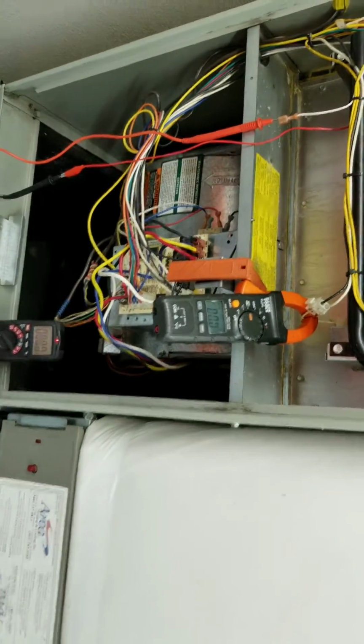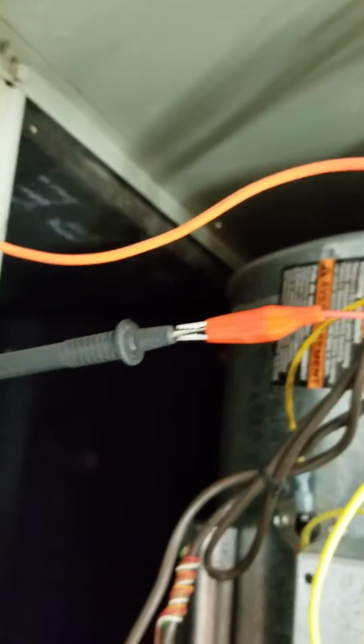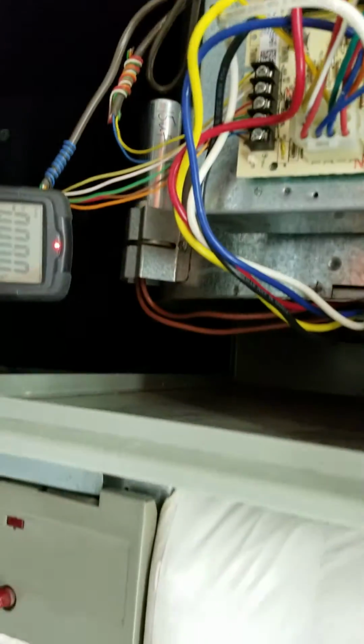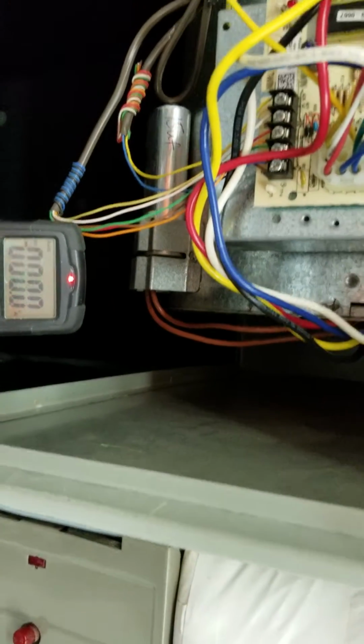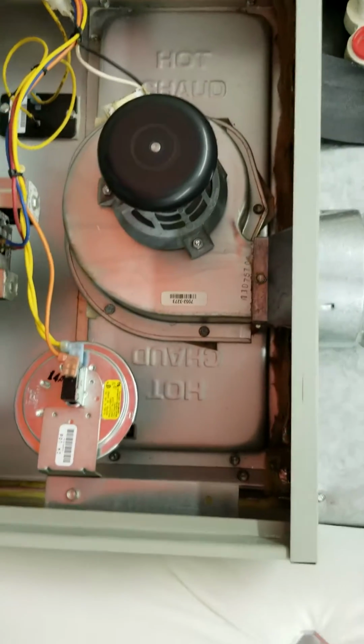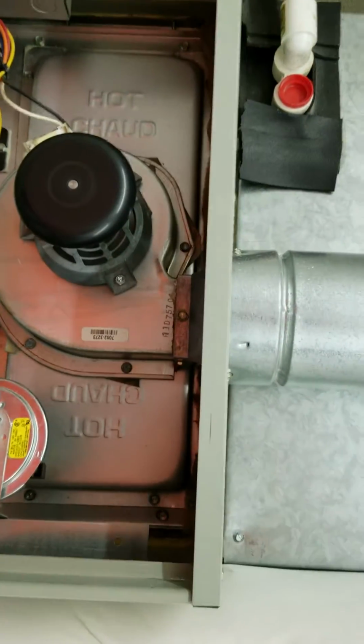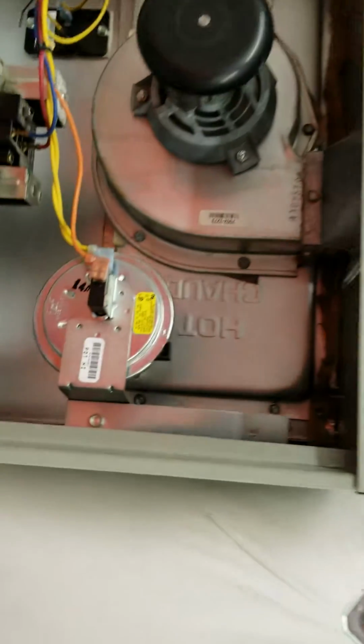Also, while you're waiting for that with the cover off, in this case you can look down inside, make sure none of the insulation on the inside of the cabinet, the ductwork that you can readily see, has come loose. If it has, you can go ahead and re-secure it. Okay, first step that's going to happen is our inducer comes on. Second step, the pressure switch proves.